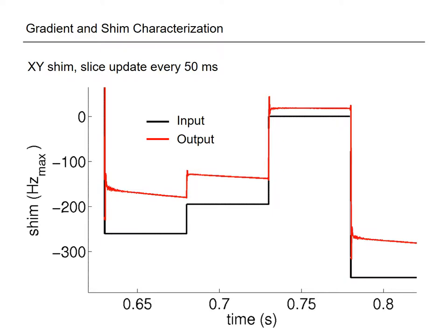And if we look at the effects of the long-living eddy currents in the time domain, here for a series of shim steps, we see how the shim field slowly converges to the desired levels.